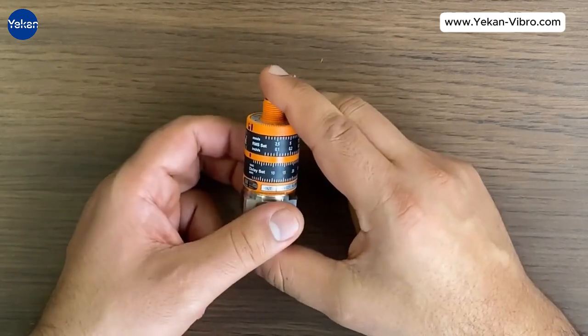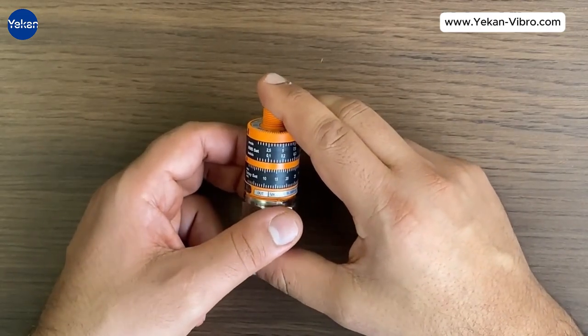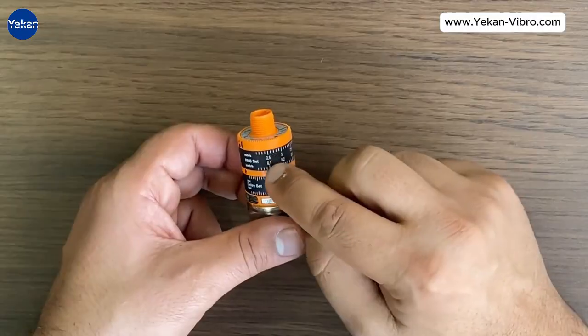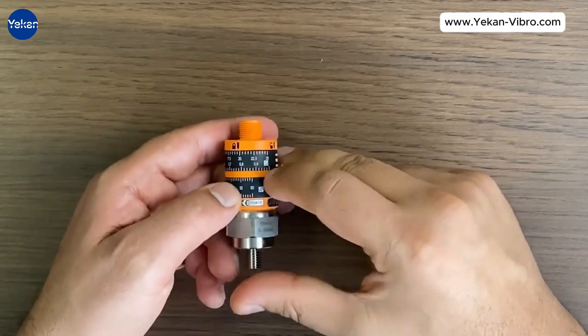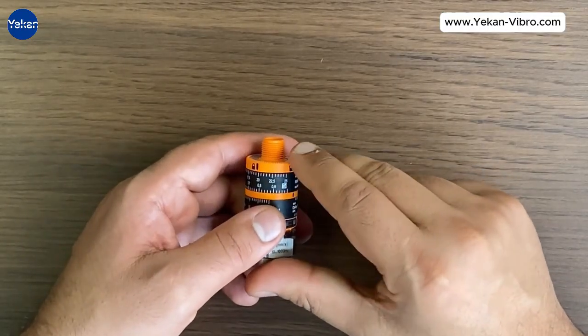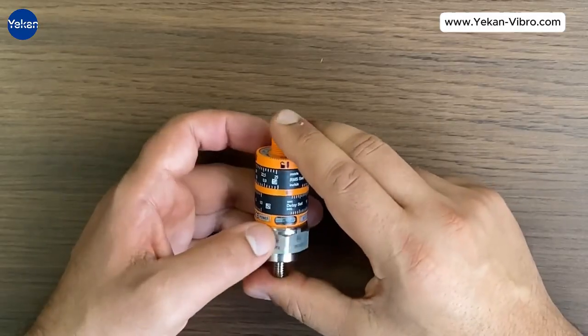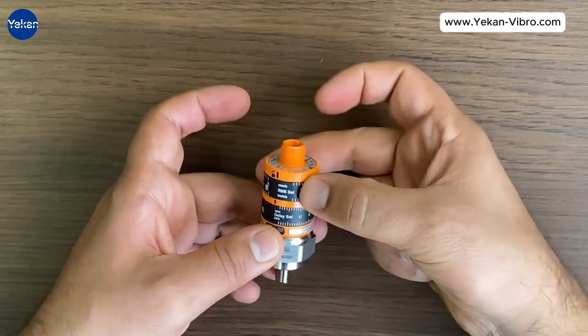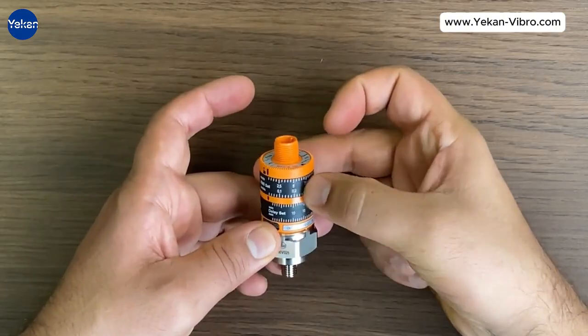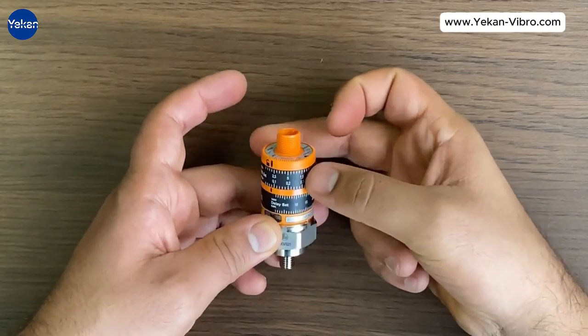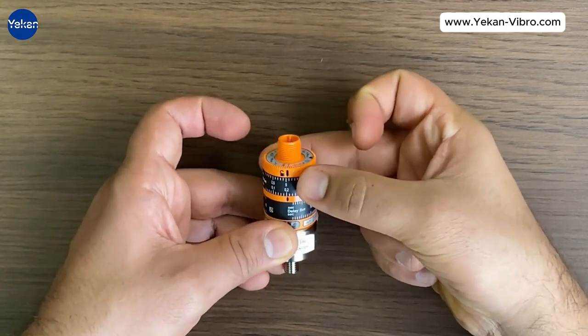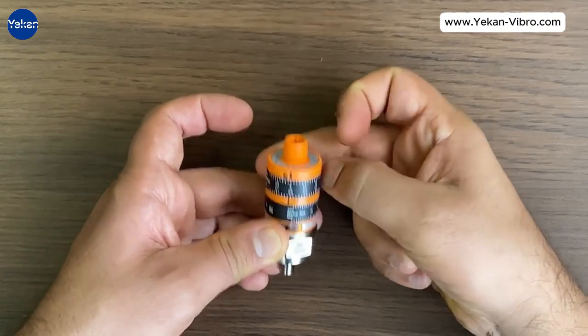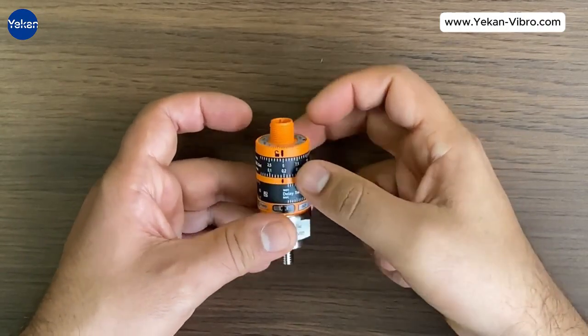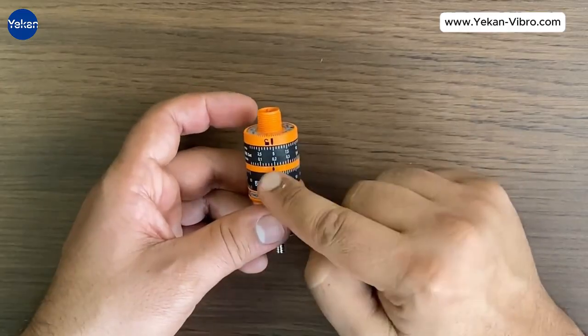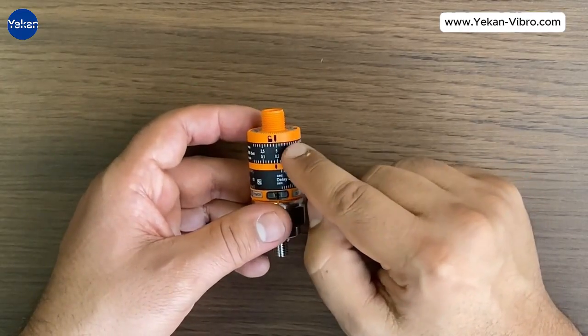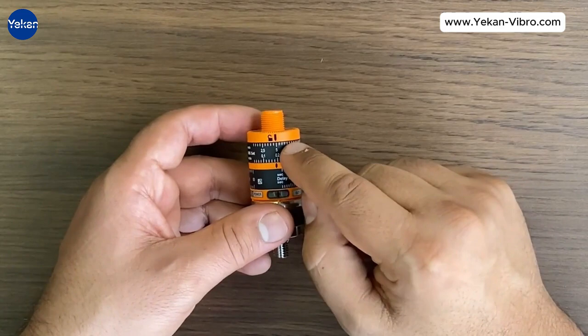This sensor, VKV021, has a reading range from 0 to 25 mm per second, which is equal to 1 inch per second. The scale starts from 0 at the top and increases down to 25 mm. You can set the set point anywhere within this range. For example, I set it to 5 mm per second. That means if the vibration level reaches 5 mm per second, the relay will activate.